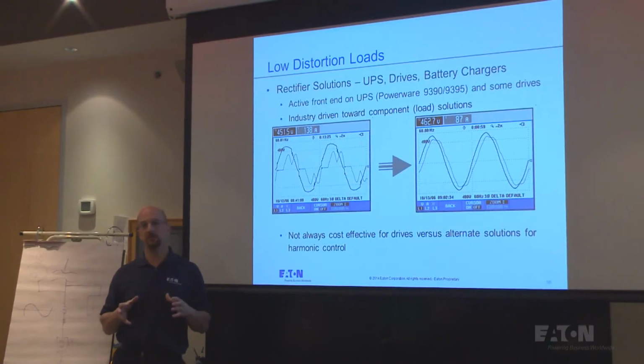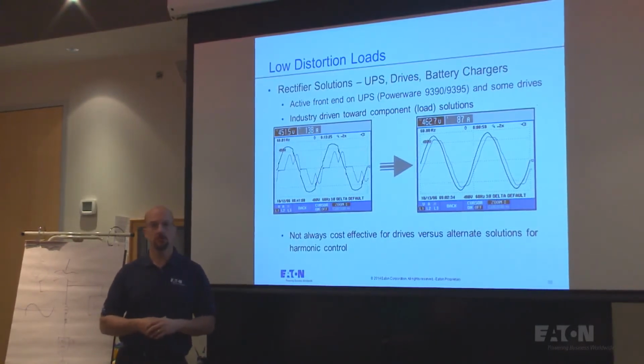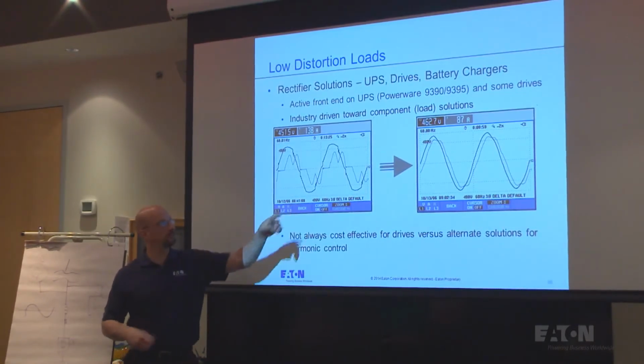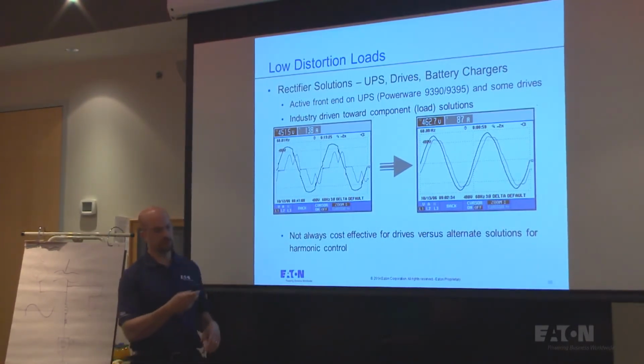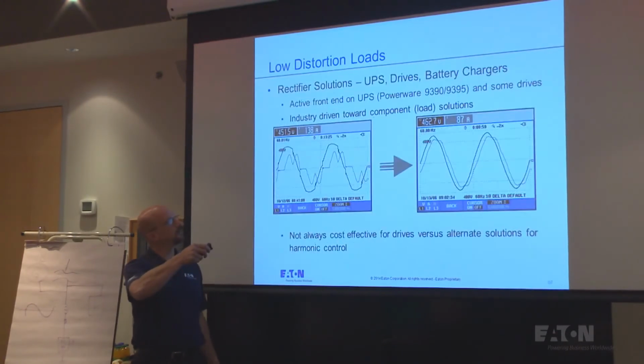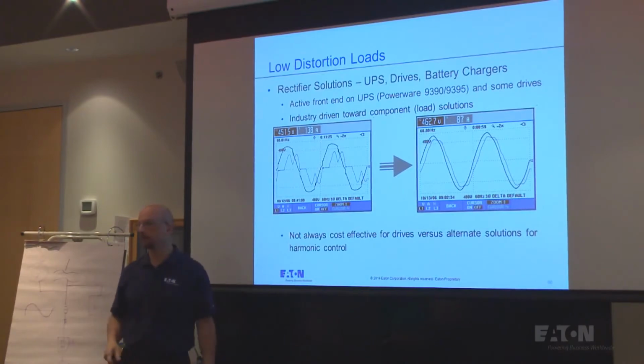So from a cost standpoint, it's the same price or less to make that front end of that UPS much better in terms of harmonic current. So this is what it used to look like with a 6 pulse, and this is what it looks like with an active rectifier.